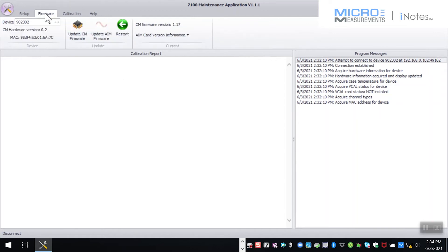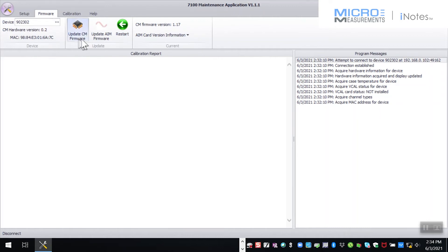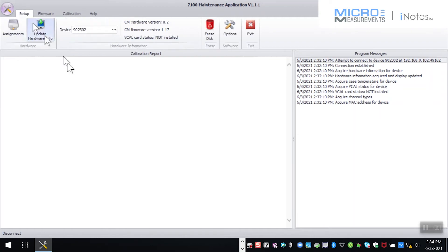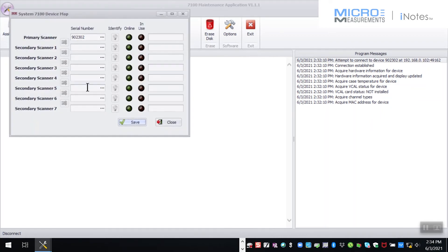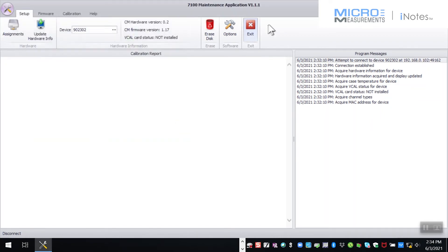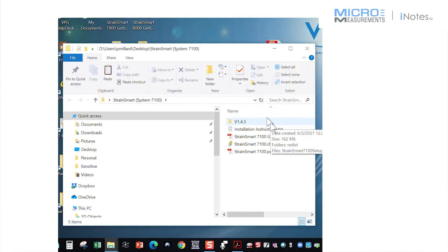So the last thing I just wanted to highlight here too is the opportunity to upgrade firmware. Whether it's because you've got an older scanner or we introduce an update, this tab right here would walk you through the ability to update the firmware on the scanners. But as I said before, even before the firmware update, the system calibration, I've got the scanner assignment completed. It knows what's out, it knows that the scanner's out there and it's online. So I should be good to go in the sense that I can close out my maintenance utility software and I can now install and or fire up StrainSmart.